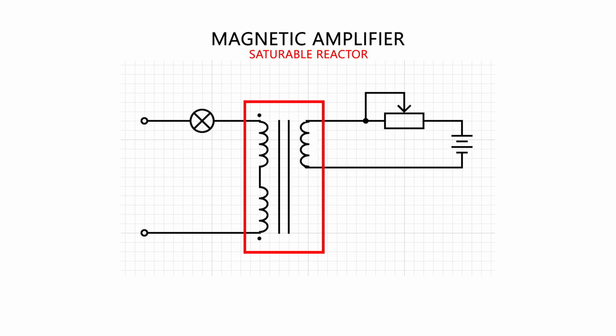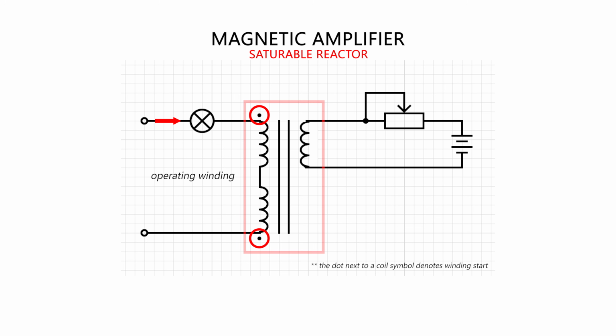Electrically, it's virtually identical to a regular transformer with 3 windings. The load to be switched, here an incandescent lamp, is connected in series with the 2 primary or operating windings. Note that these windings make a subtracting, also called series opposing, connection. This is necessary to prevent the generation of an EMF in the control winding. The combined magnetic field they create will be 0, and the device will not behave like a conventional transformer.